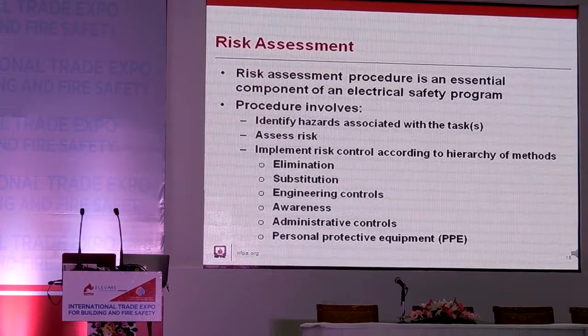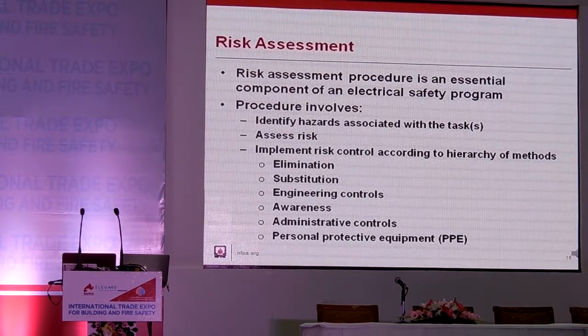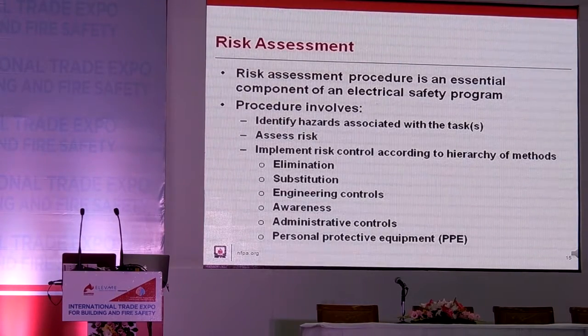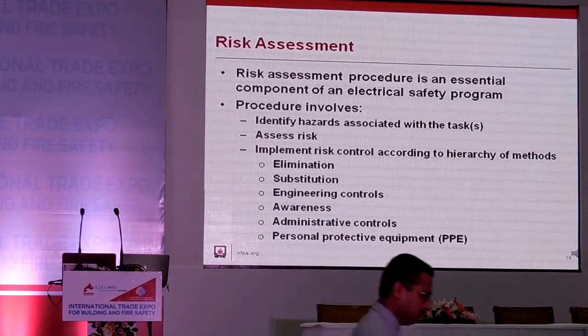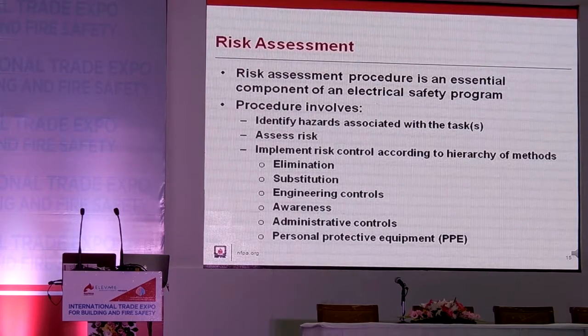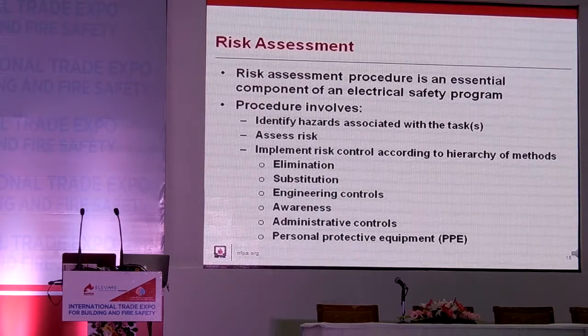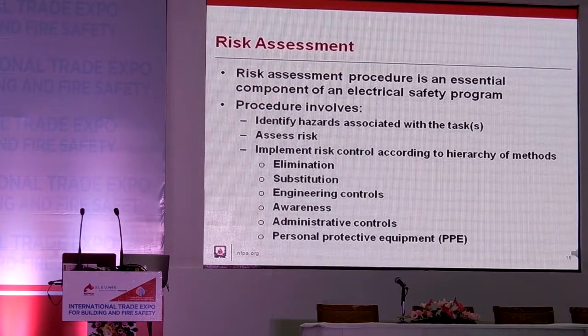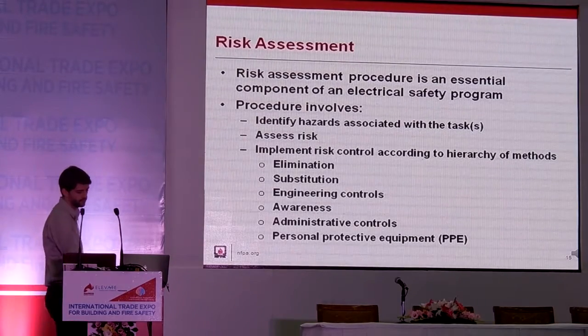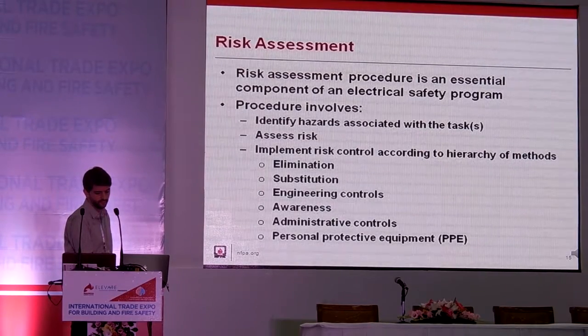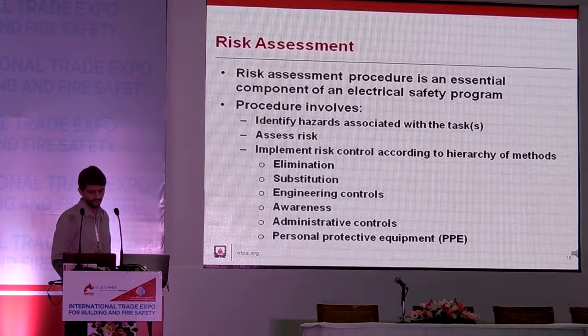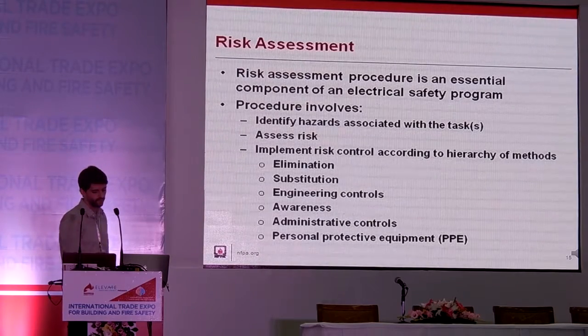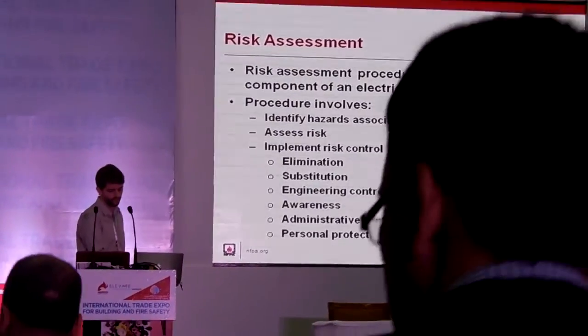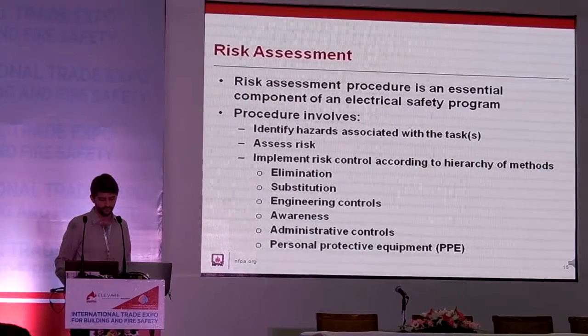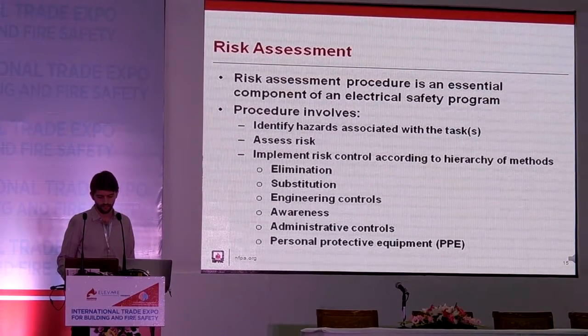Engineering controls such as insulation and isolation that prevent accidental contact with energized parts is another form of control. Awareness in the form of signage or alerting systems can help protect workers. Administrative controls such as energized work permits, such as training, help employees protect themselves against shock hazards. And then finally, personal protective equipment. When using personal protective equipment, we're doing so because we are exposed to energized parts, but properly selected personal protective equipment will protect the worker against the shock hazard. So these forms of control go from the most effective to the least effective, but in all cases, they are providing some level of protection to the employee.